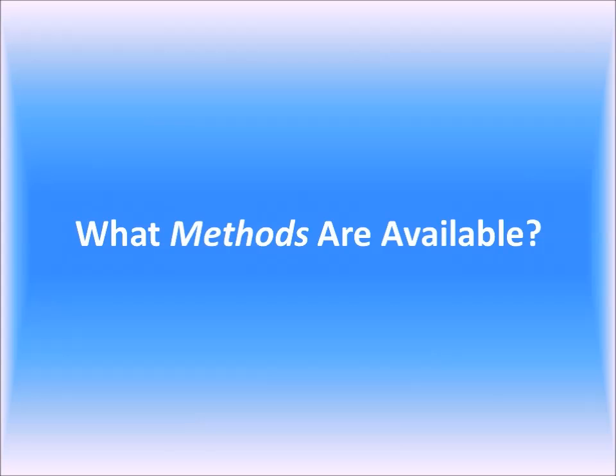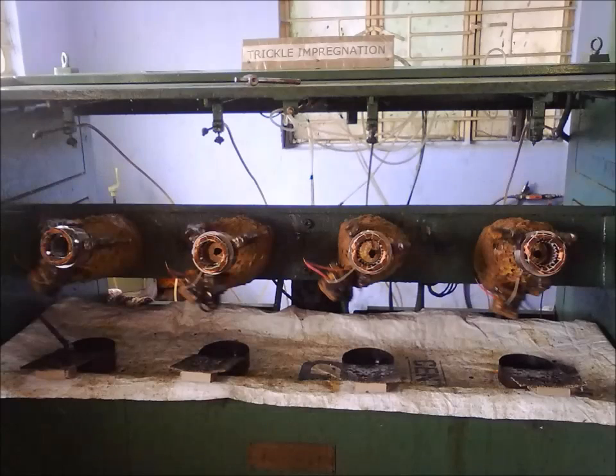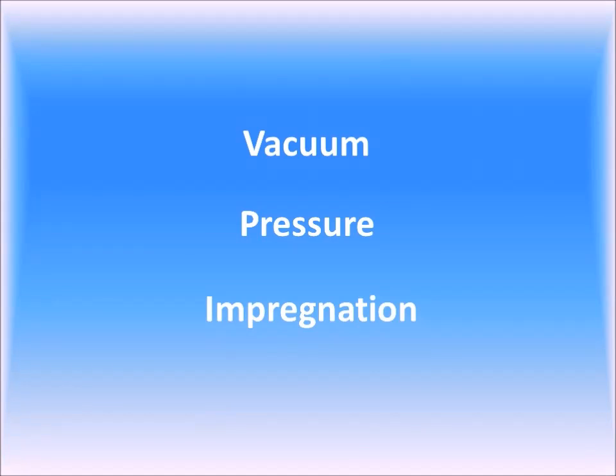So what methods are available? There are various impregnation methods available, chosen based on such factors as the voltage of the machines and the cost of the system. For example, many low voltage manufacturers use hot dipping technology or trickle impregnation. However, for our purposes, we will be discussing a method known as vacuum pressure impregnation, or VPI, which involves the use of a vacuum and pressure, as the name implies, along with a resin instead of the traditional varnish, and is primarily used for high voltage motors and generators.